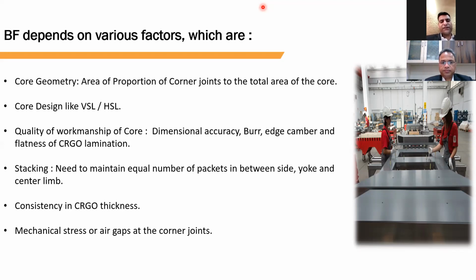One more point is mechanical stress, which we can avoid during our process, as I mentioned during slitting too. Something new about mechanical stress: if the CRGO processor plans their CRGO cutting properly, and doesn't stack everything on one pallet but distributes the cut lamination in a ready-to-use pattern, then these good practices can reduce mechanical stress. We have seen that due to high production load, they just pile CRGO lamination on one pallet itself, which impacts the bottom side of the CRGO. Such practices should be avoided so we can improve this stress factor.